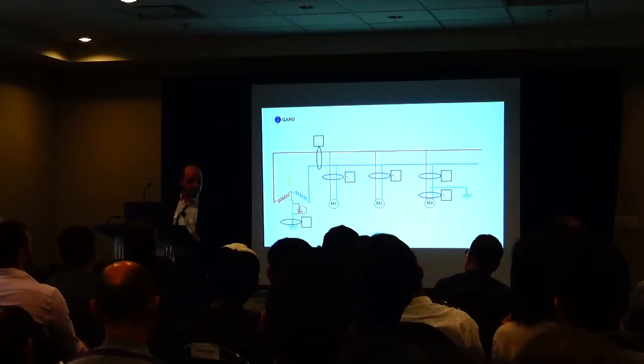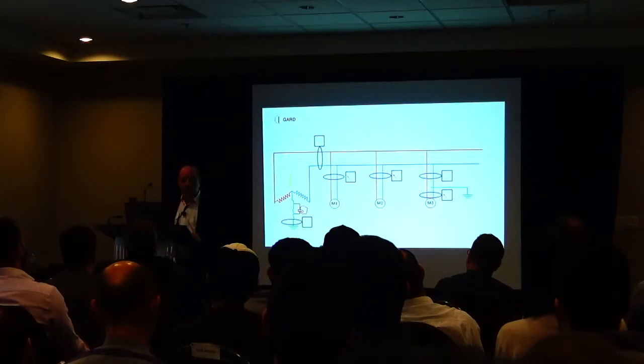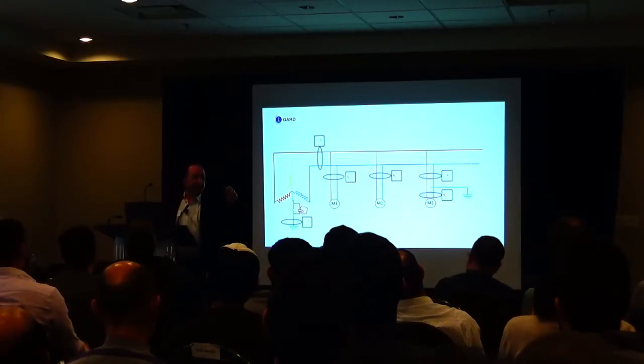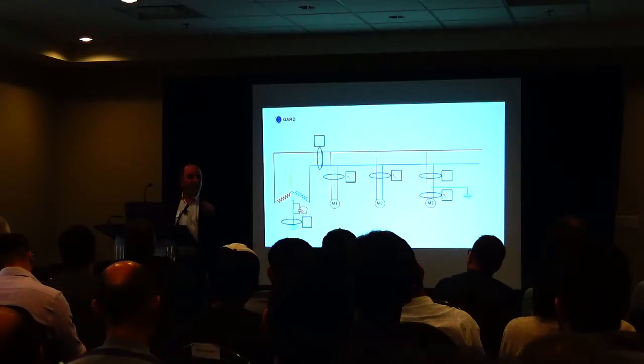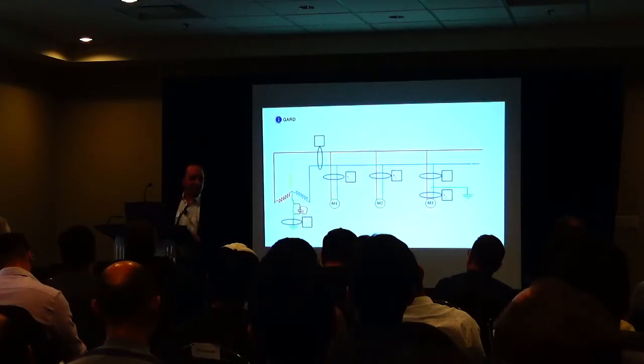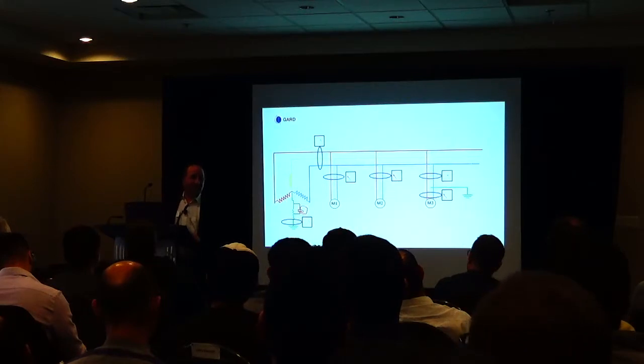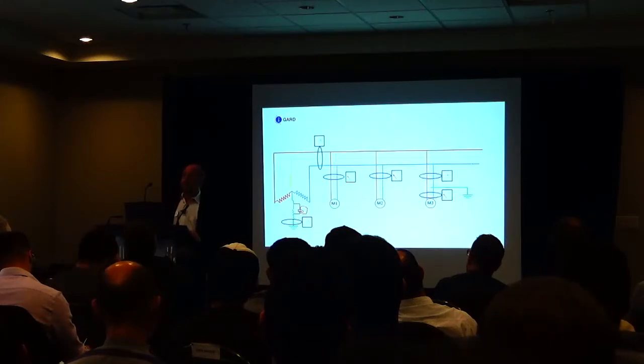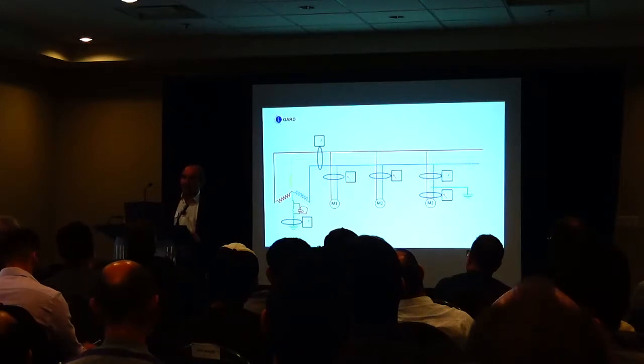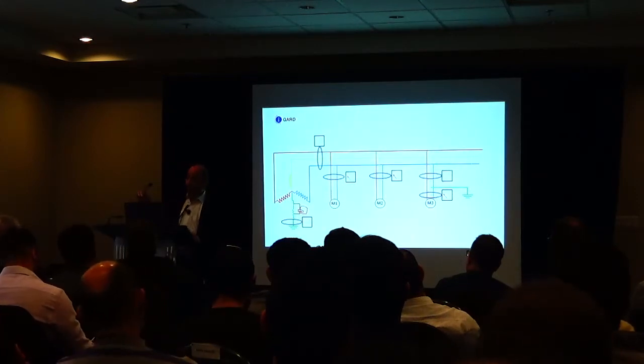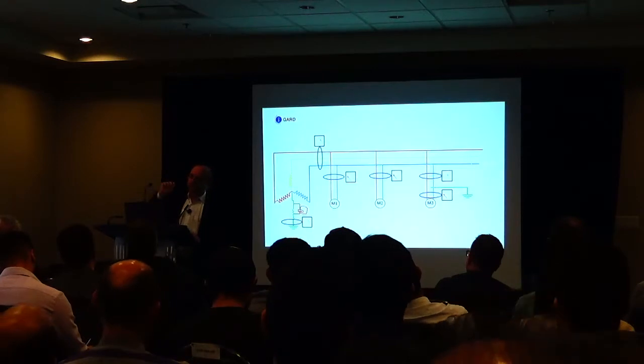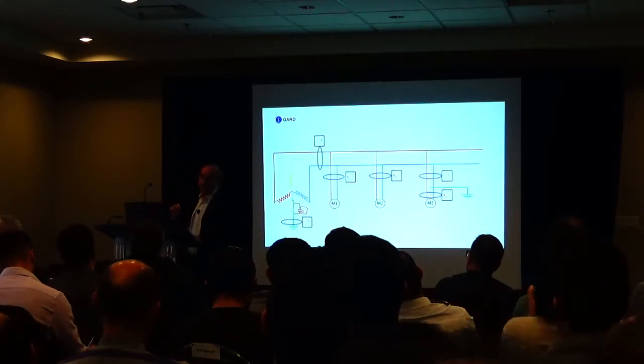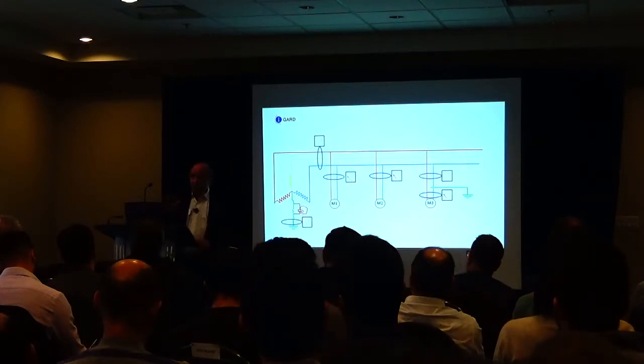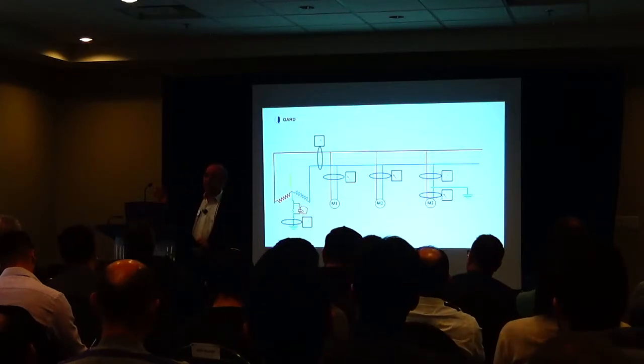Right? So, have we done him any favors? He's done everything properly. He's done everything he's been trained to do from the day he became an electrician, and he got electrocuted. Why? Because the Canadian Electrical Code allowed a distributed neutral on a resistance grounded system. Now, I don't think any have been used, but there's a danger in that being done. This is why you disconnect the neutral and you get the full benefits of having a resistance grounded system, because you don't have to trip. Your neutral is never going to become energized because you don't use a neutral.